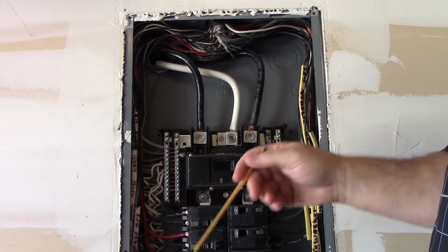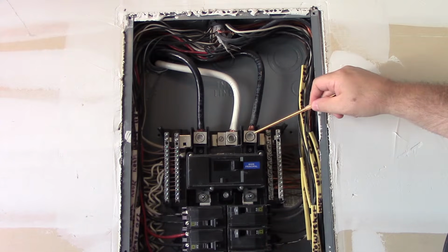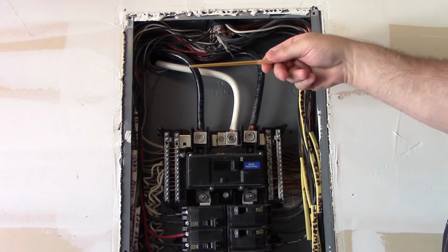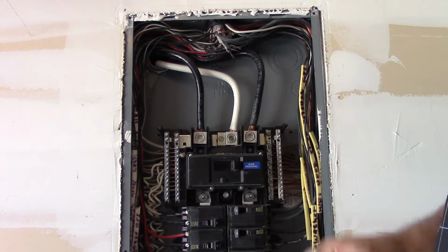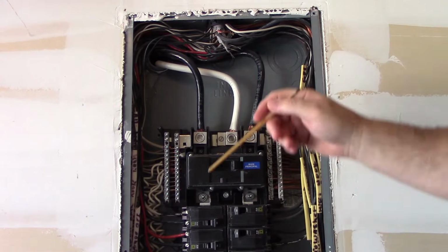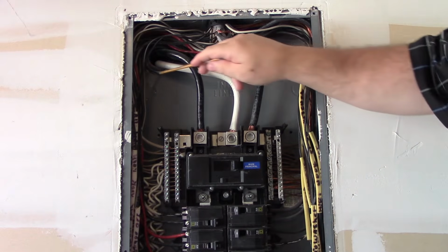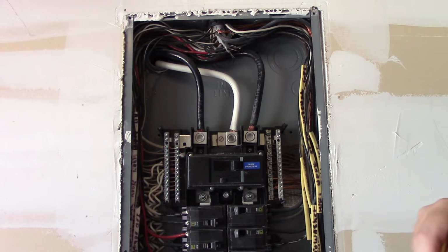And again, unless they pull the meter, these are energized parts right here. These are live. So when you pull it loose, it could be a little hairy, and I don't want any homeowner to think they can do that. So call this out as you see it. Again, that's a violation of 300.4(G) of the National Electrical Code.